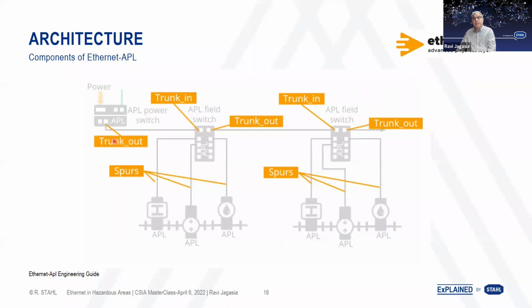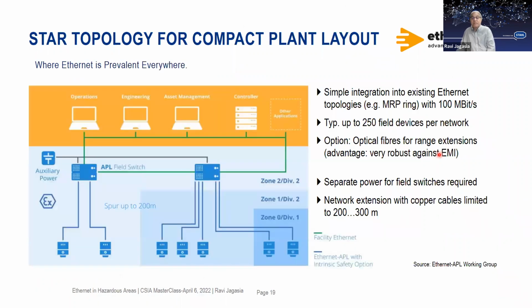And then the standard topology, the trunk in and trunk out, so you can loop this up. The spurs come out to the APL field device, not the foundation fieldbus field device, but the APL field device. So this is, I would say, the basic structure of the Ethernet APL. What more can be done, and how do they classify with the hazardous area, is that you could have a commercially available Div 2 or Zone 2 valid Ethernet backbone of field switches, which could be in the Div 2 area, connecting to the field devices, which could be sitting in Zone 0, Zone 1, or Div 1 environments.